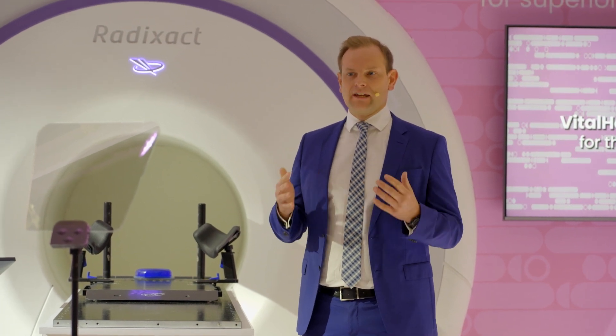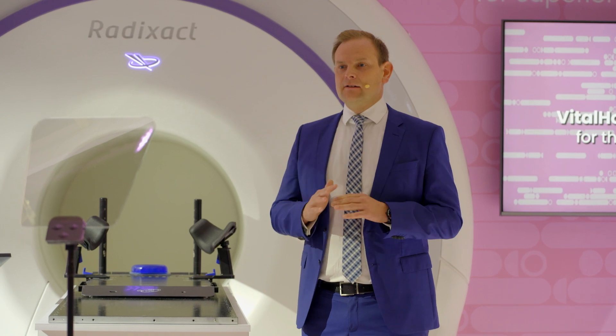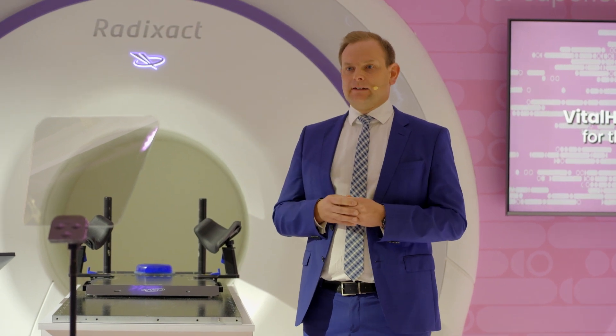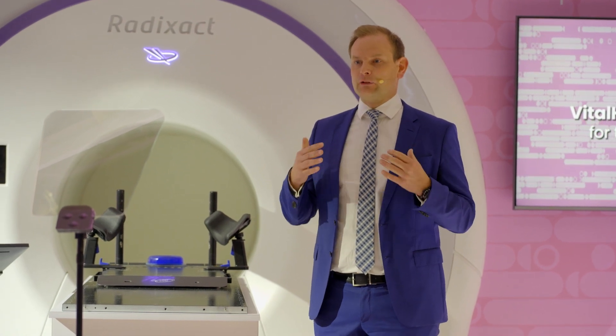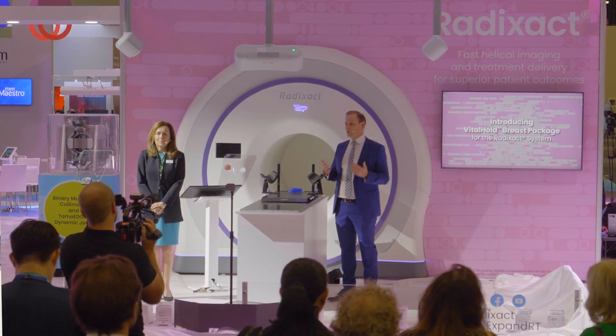Catalyst Plus HD projects visual guidance directly onto the patient's skin for easy setup and positioning. Given the ability for correction of posture inaccuracies completely without tattoos, markers, and fiducials, we aim for a more efficient patient setup while reducing the need for X-ray imaging. Once the patient is correctly set up, the treatment starts. The system continuously monitors patient movement throughout the treatment to ensure accuracy and confidence that the treatment beam is only on while the patient is in the perfect position. For breast cancer treatment in particular, our workflow for deep inspiration breath hold treatment has fantastic results, both for treatment teams and for the patients.